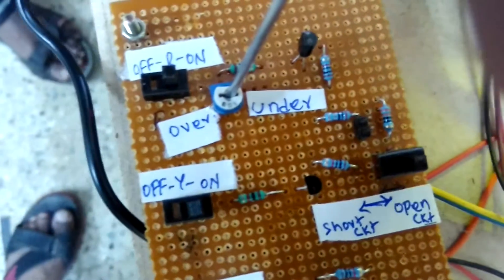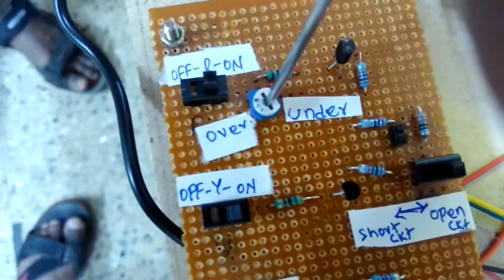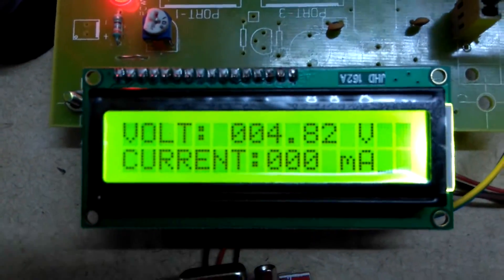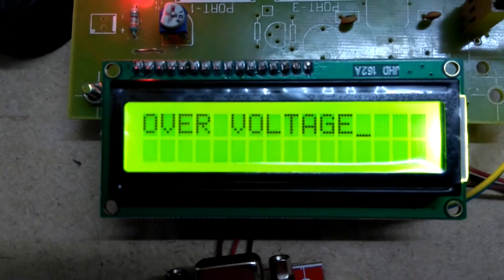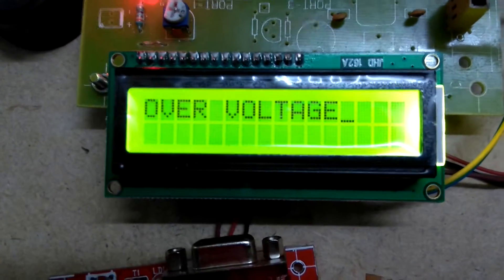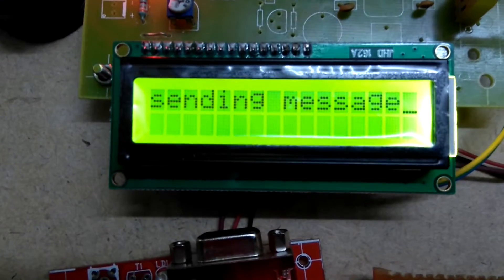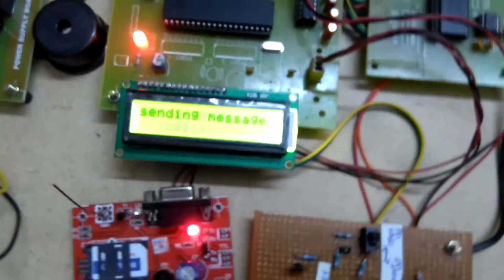If you rotate this preset towards over-voltage, it is indicating 4.82 — that is over-voltage. Similarly, you will get the SMS indicating that on that phase something has happened, meaning over-voltage is occurring.